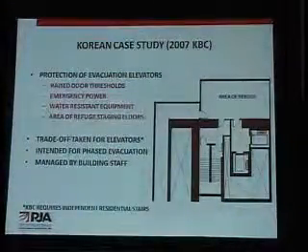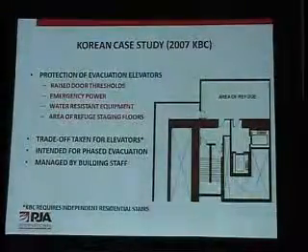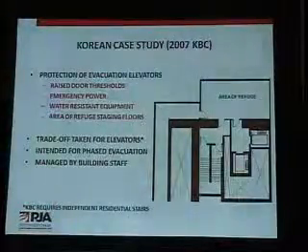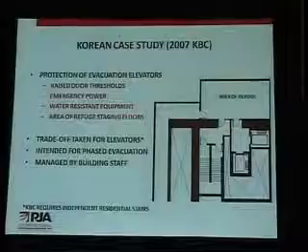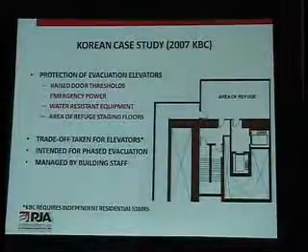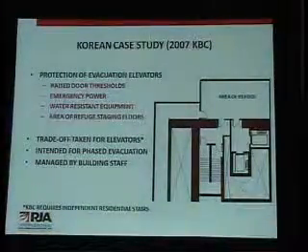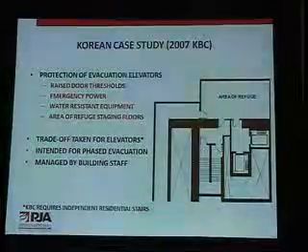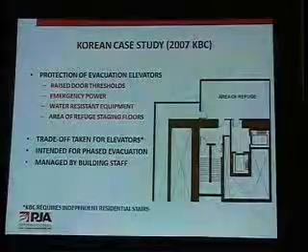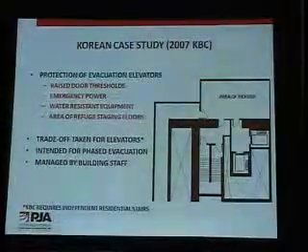And the last example I wanted to give you was the South Korean case study. This is a super tall project in Incheon, where you can see the Korean standard being enforced, where you have separate vestibules, one for the stair, one for the elevators. They did not require the stair to be broken as it has been, but we insisted that the stair provide a way into the vestibule and back out of the vestibule, and we can create signage there to identify the area of refuge.